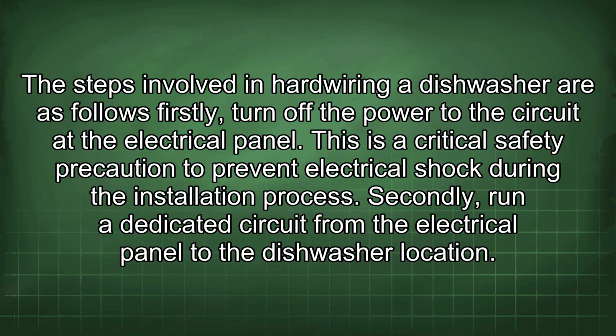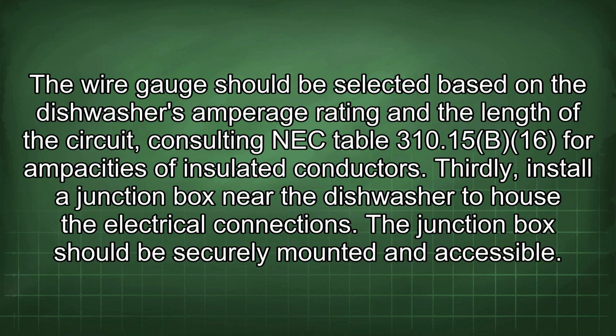The steps involved in hardwiring a dishwasher are as follows. Firstly, turn off the power to the circuit at the electrical panel. This is a critical safety precaution to prevent electrical shock during the installation process. Secondly, run a dedicated circuit from the electrical panel to the dishwasher location. The wire gauge should be selected based on the dishwasher's amperage rating and the length of the circuit, consulting NEC Table 310.15(B)(16) for ampacities of insulated conductors.